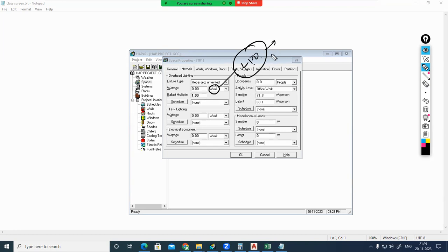This LPD value can be taken from any ASHRAE Fundamentals, chapter on non-residential heating and cooling load calculation. Once in every 4 years ASHRAE revises the Fundamentals. Any Fundamentals, non-residential cooling, the chapter they have provided is heating and cooling load calculation. Or our energy standard, ASHRAE 90.1 standard. From the ASHRAE 90.1 standard, we can consider the per meter square lighting load.